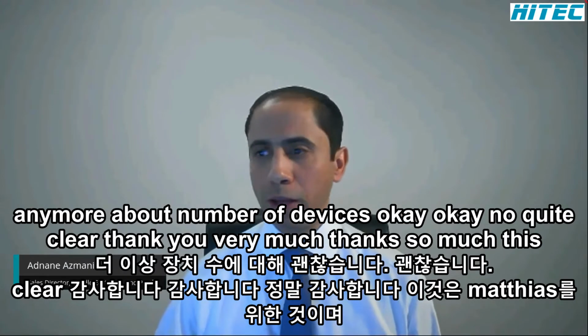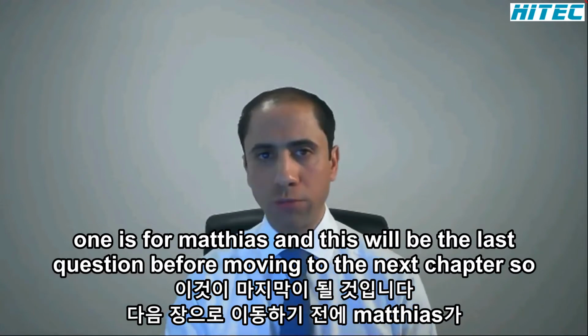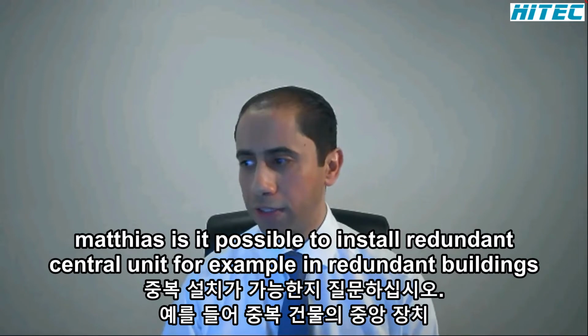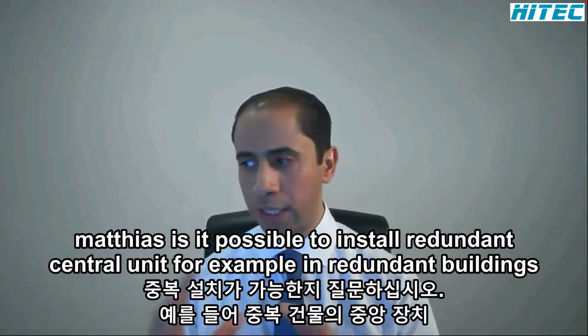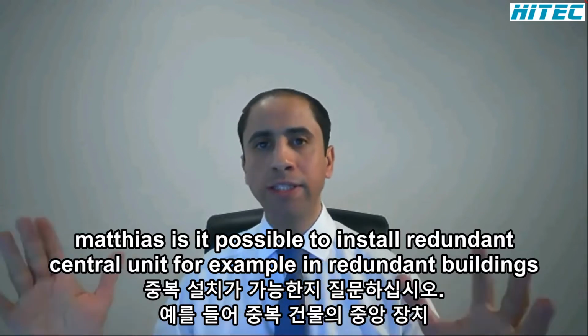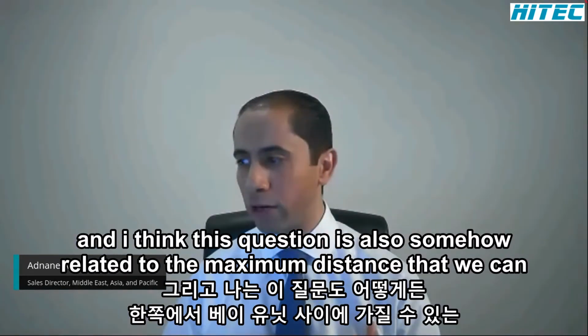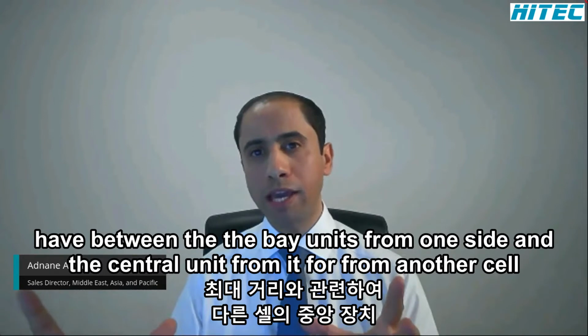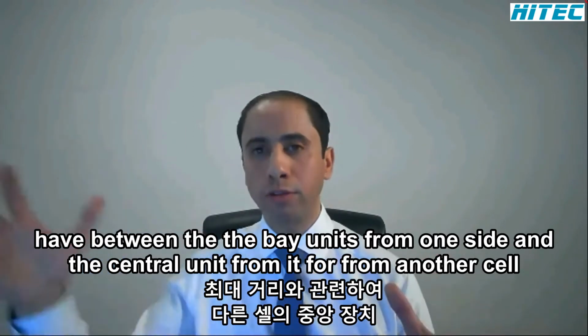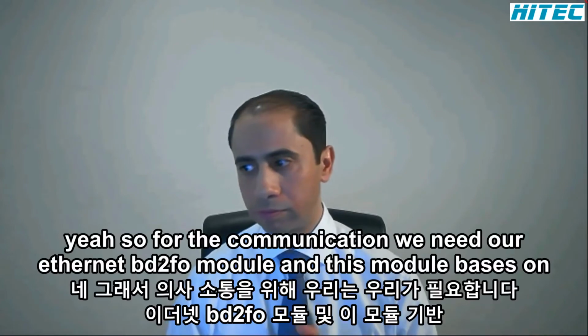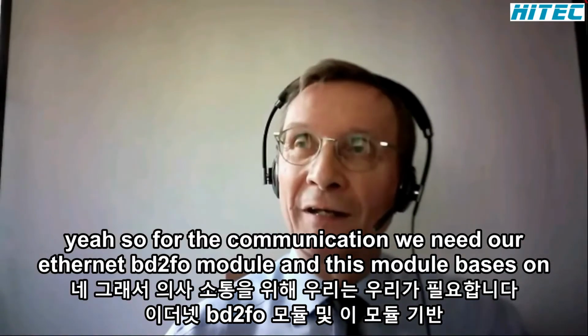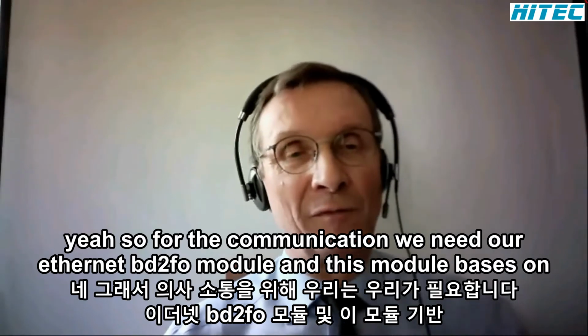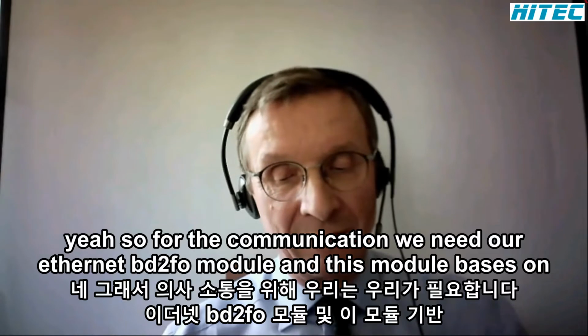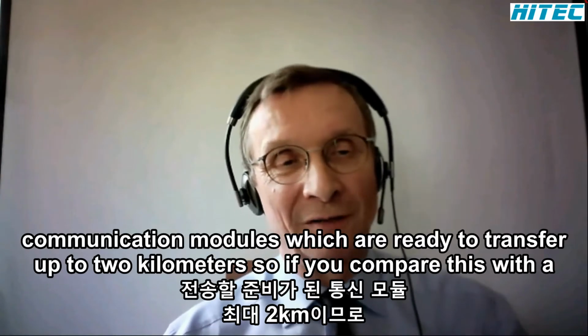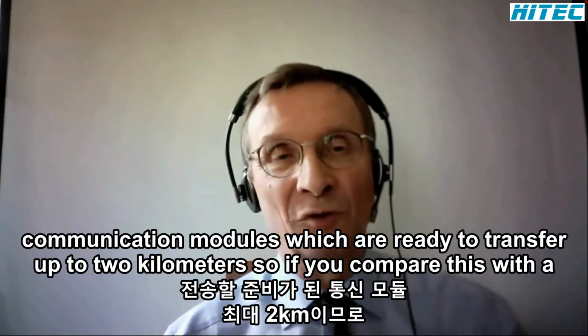Thanks. So this one is for Matthias, and this will be the last question before moving to the next chapter. Matthias, is it possible to install a redundant central unit, for example, in redundant buildings? I think this question is also related to the maximum distance that we can have between the bay units on one side and the central unit on the other side. For the communication, we need our Ethernet 2FO module, and this module is based on communication modules which are ready to transfer up to 2 kilometers.